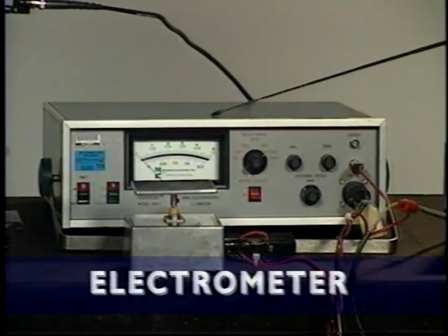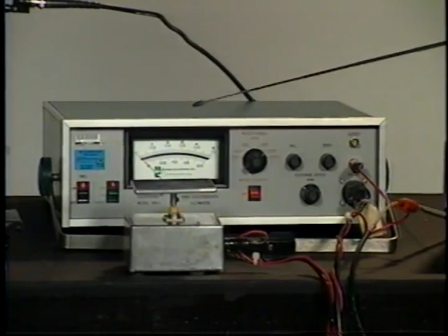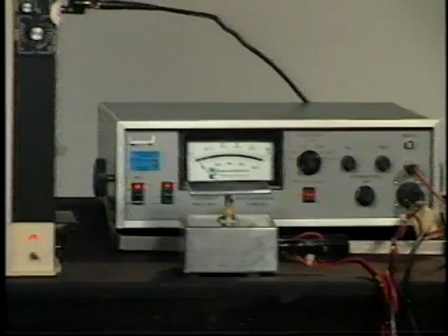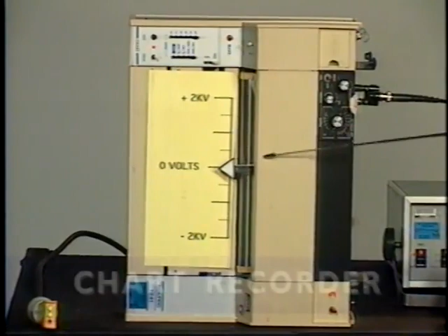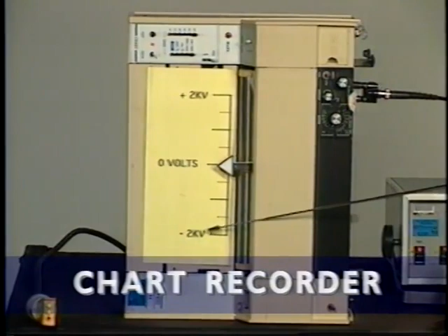I will now explain the equipment that makes the measurement over here on the table. This is the main unit of the electrometer, and the electronics inside decide what voltage it has to provide to the electrometer head. Once it makes that decision and outputs it on the meter, we also record it on the chart recorder here, with zero volts at the center. It goes up to plus 2 kilovolts and minus 2 kilovolts, and now we see an output of what the voltage is on the electrometer head.